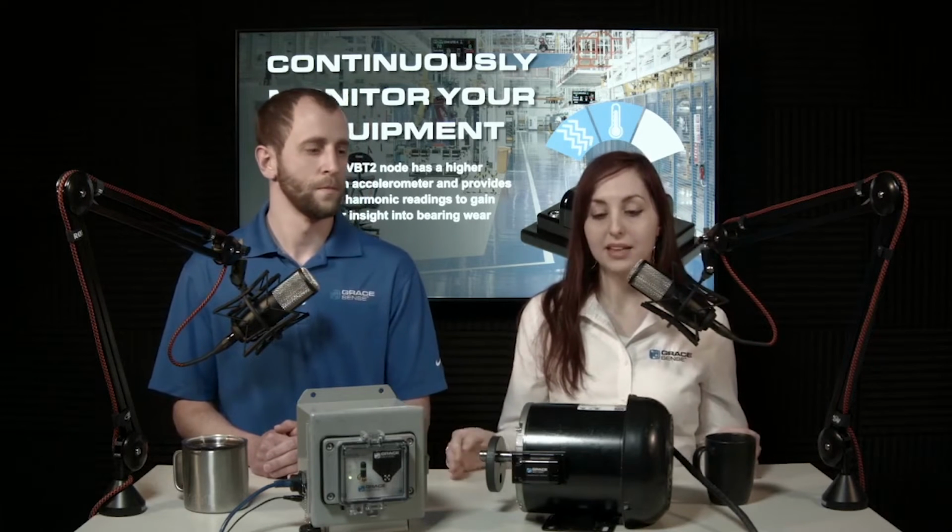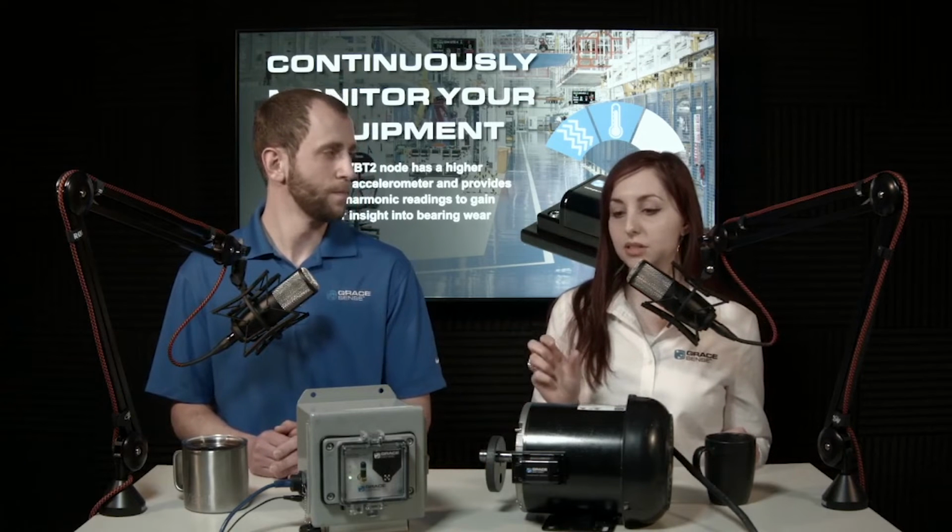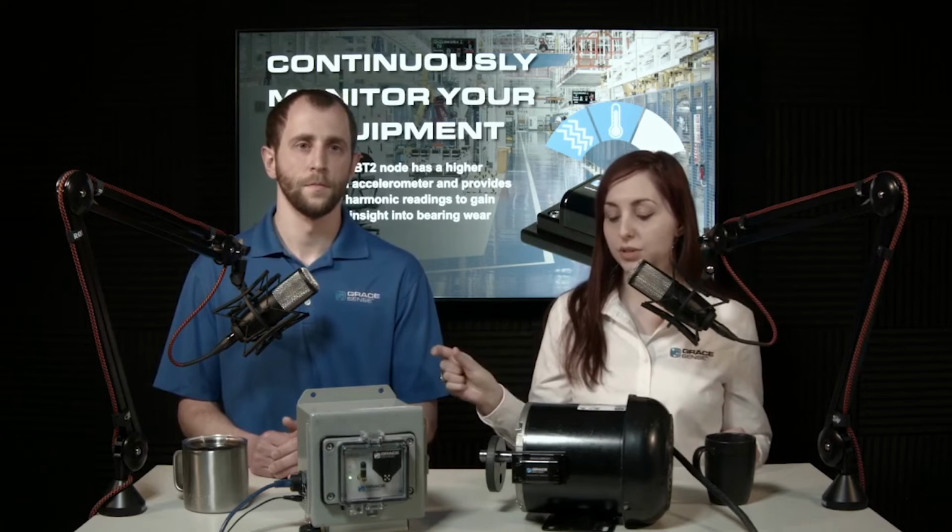Yeah. So what does GraceSense offer? There's a lot of different options out there, so where do we sit? Yeah, so GraceSense offers a comprehensive banded analysis, is how we call it. So we monitor vibration across a wide spectrum, and then we split the spectrum into different frequency bands, and then we report the vibration that each band contains individually.